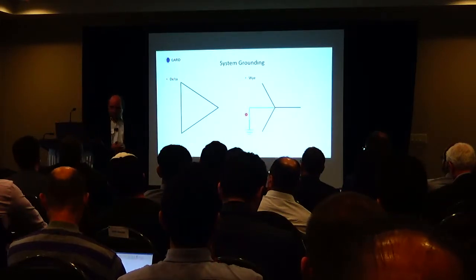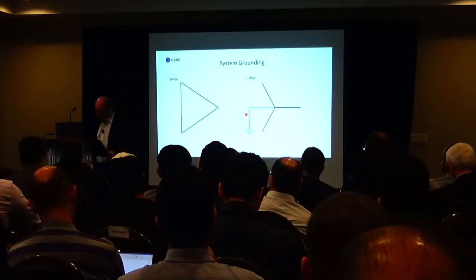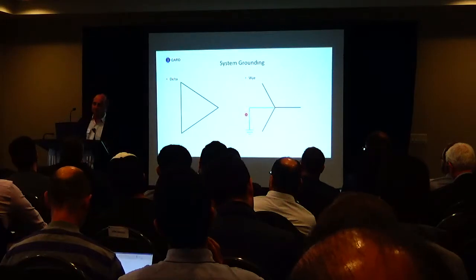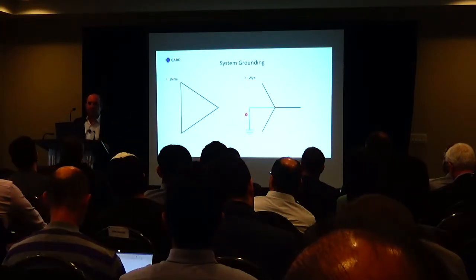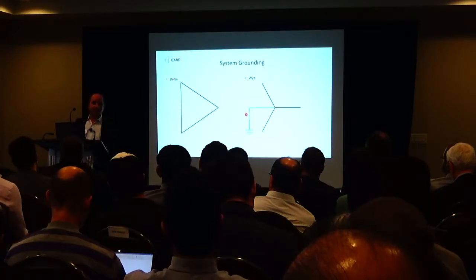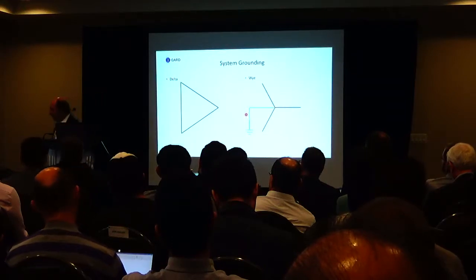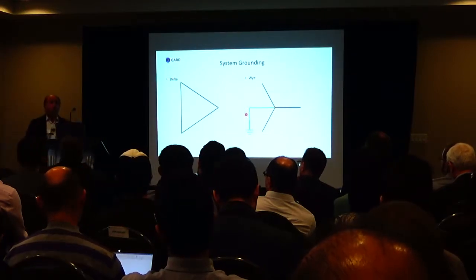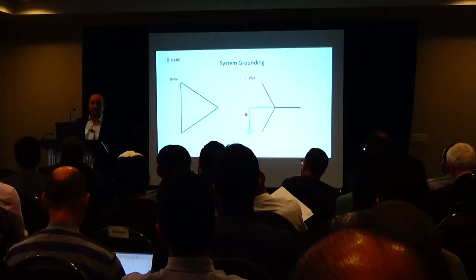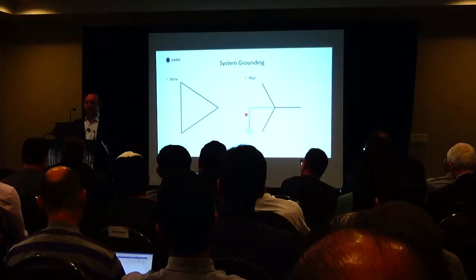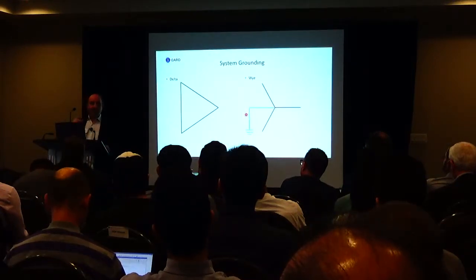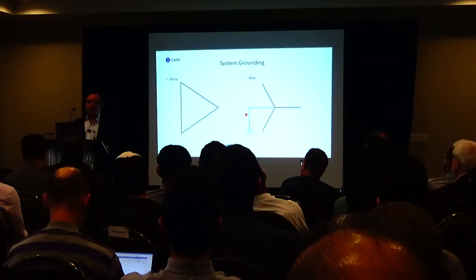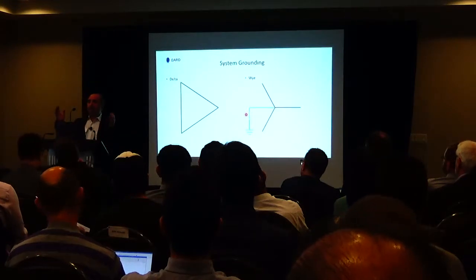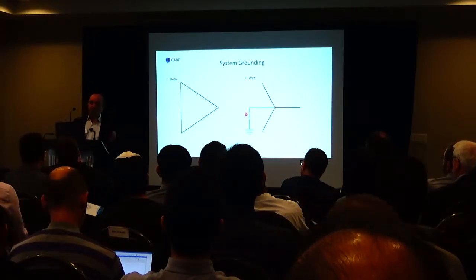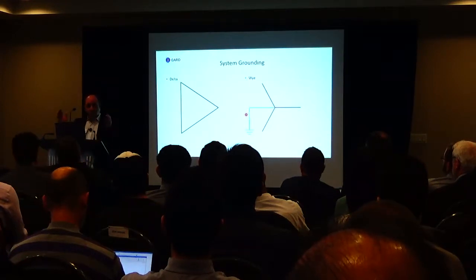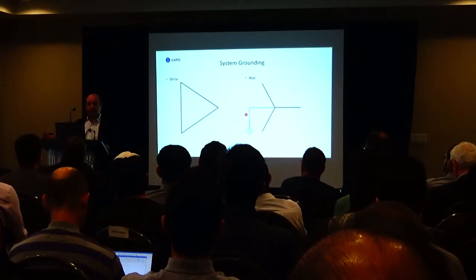Now a resistor, a 69 ohm resistor, will be very, very small, and it protects the entire secondary of the transformer. Whether it's a 500 kVA transformer or generator, or 5 MVA transformer or generator, one resistor this size, or half this size really, will protect the entire secondary, so the entire distribution system is fully protected as an arc flash mitigation technique. Unlike, who uses arc flash relays? We produce arc flash relays. The problem with arc flash relays is that they only protect a section of gear where you have the arc flash mitigation. Differential protection only protects a certain portion of your gear. The resistor protects the entire secondary.